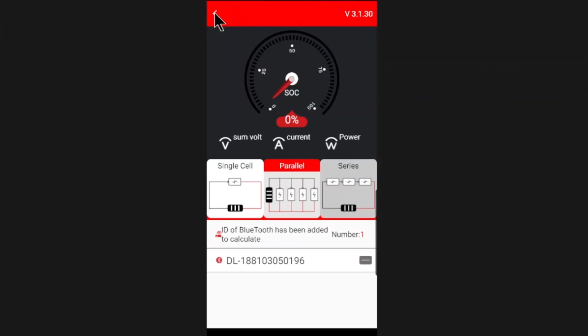Now let's check a few things: that the sum voltage matches what we measured, which is 13.3, and importantly that the temperature shown is correct for where you are. Then check the 4 cell voltages to make sure they're more or less what we measured before.